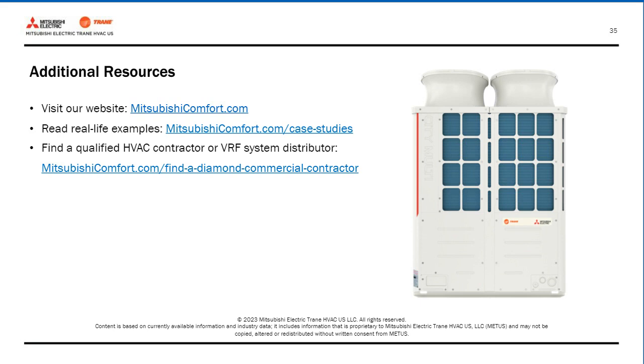But there was a question that snuck in after our last question, but I think we should answer it. Just indulge me for one moment. So with New York and other states moving away from fossil fuels, is Mitsubishi Electric working on lower temperature heat pumps, since we see negative 20 degrees or lower? Yes, we are. We rate our cold climate heat pump systems. One of the rating metrics we use is, can it deliver 100% capacity at a given temperature? We started off with 5 degrees Fahrenheit, where we could maintain 100% capacity. Now we have systems rated to deliver 100% of the rated capacity down to negative 10, and we keep on pushing that boundary.